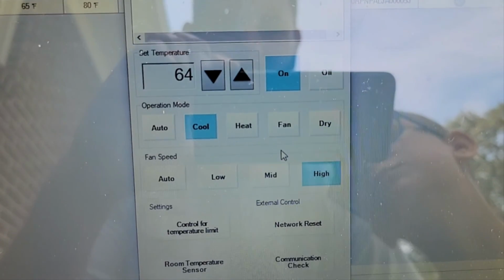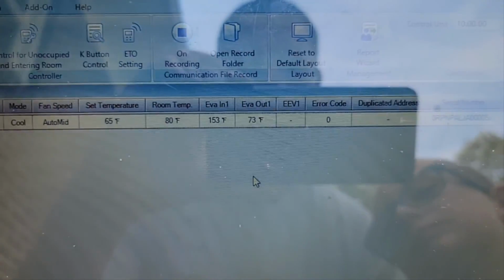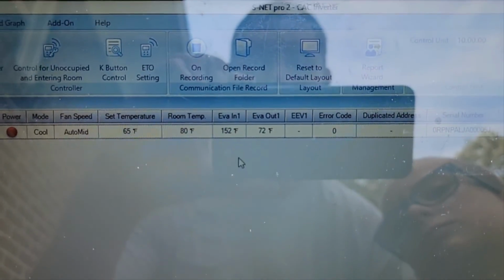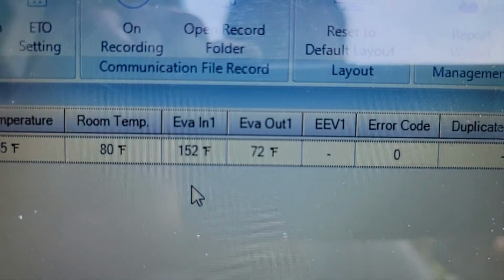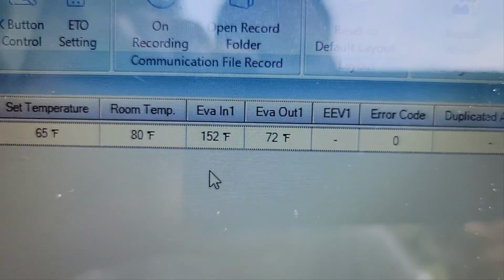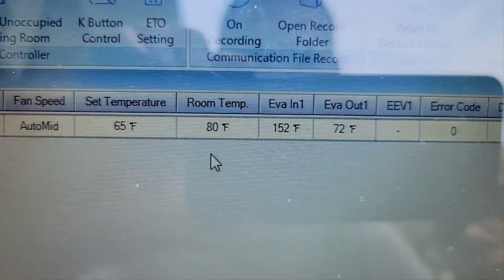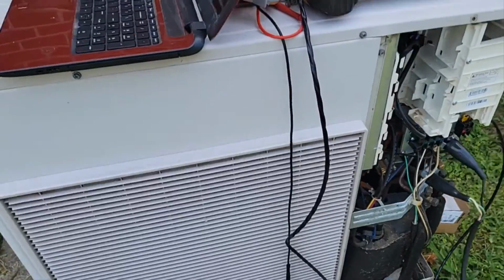All right, now that we've got it in cooling, unit should come on. We'll wait till it comes on, and then I will show you what the EEV does. And you can see evaporator inlet temperature is 152, and you know that's not correct. Room temperature is 80. All right, equipment's coming on.